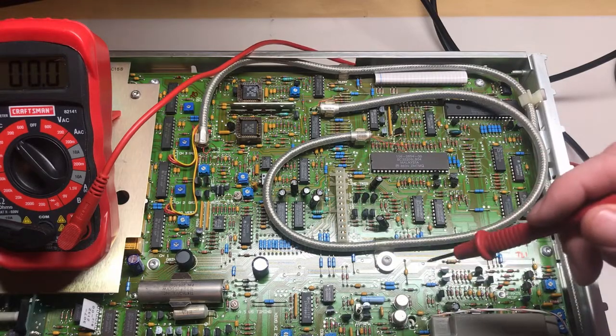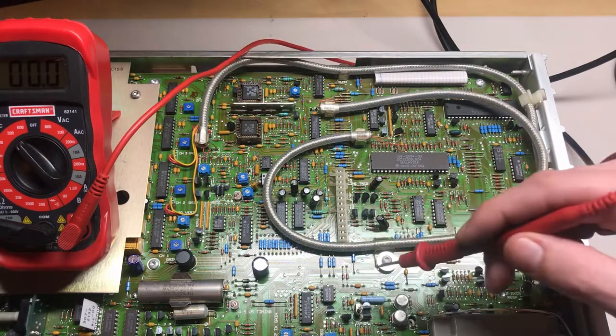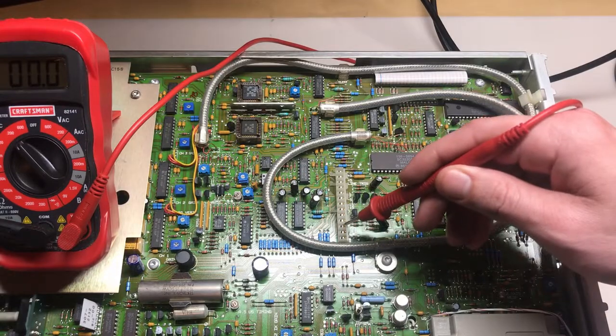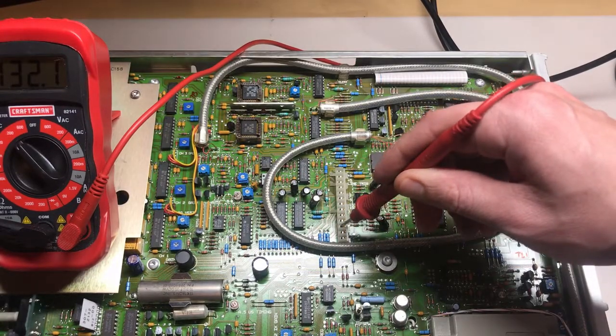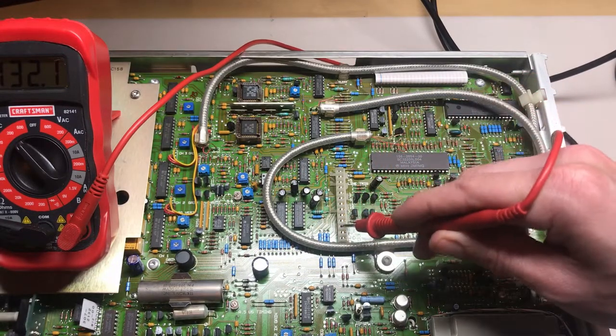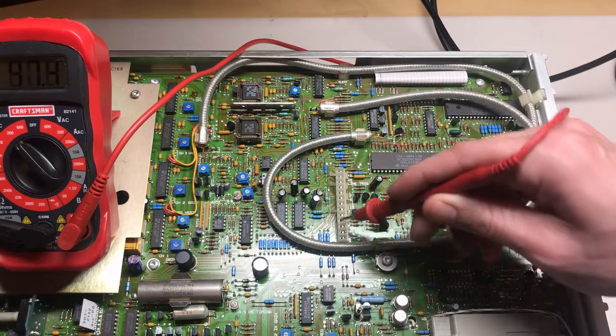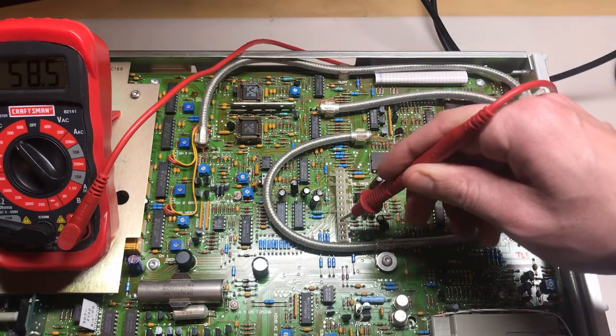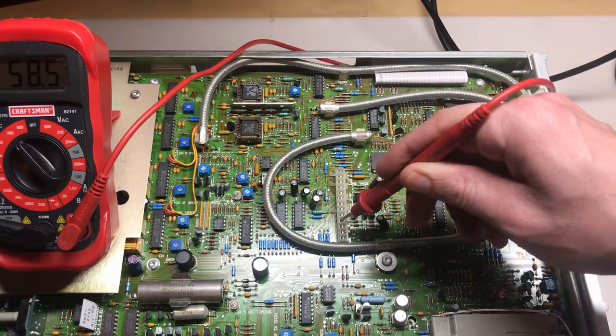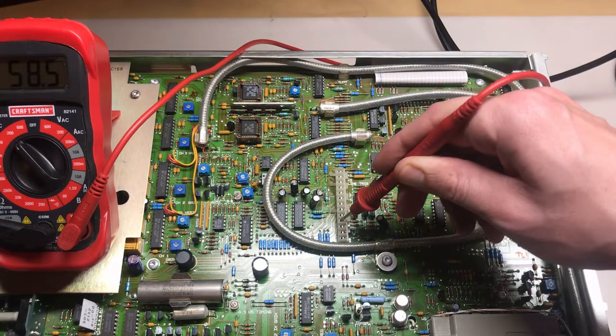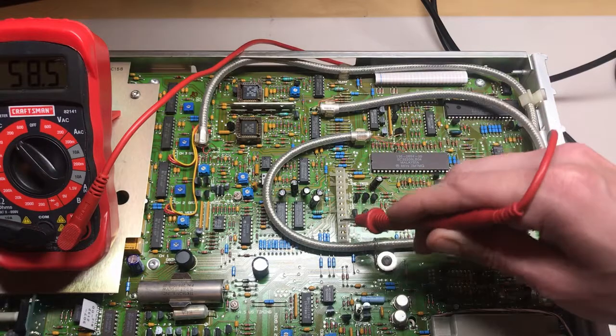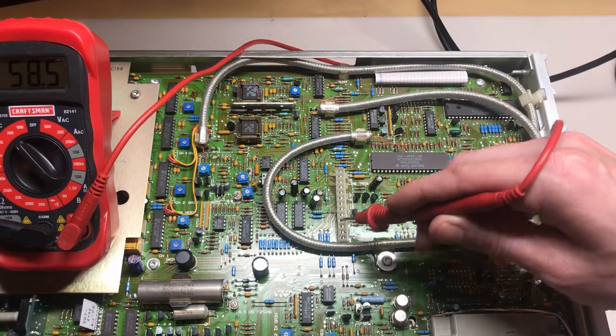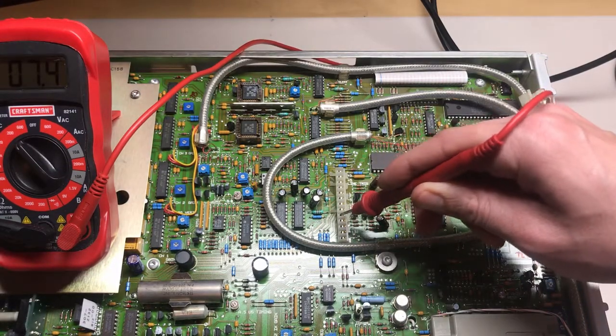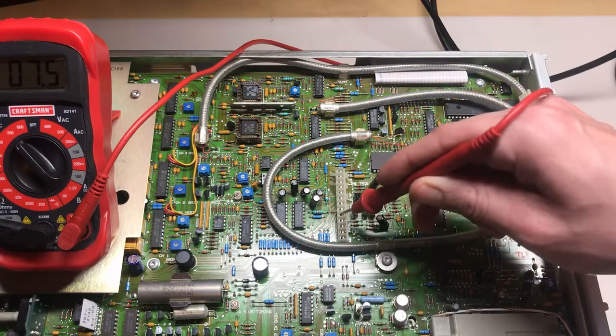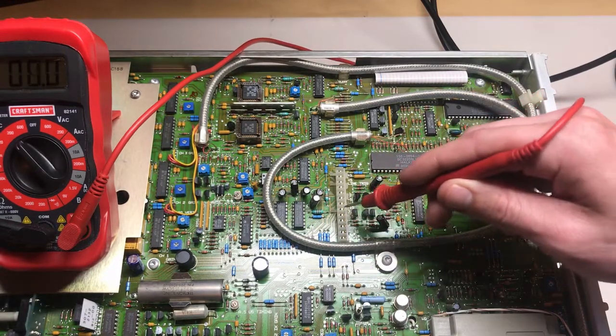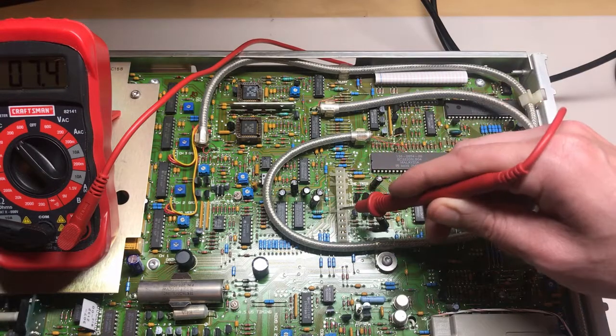The bottom one is AC, it's 100 volts. The second pin up is ground. Third pin should be 130 volts DC. That looks good, about 132. Next pin should be positive 55. Slightly high. Nothing too concerning. 58.5. Maybe a concern, but it's there. Next pin, tough to see. Maybe 7 volts, yeah, minus 7 volts, that's good. Next pin looks to be positive 7, looks good.